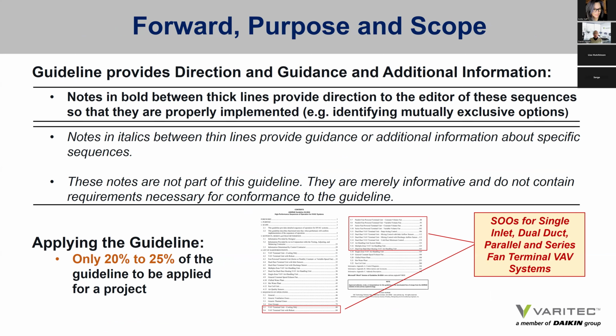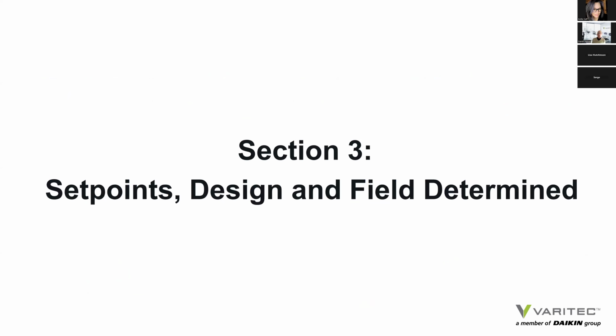The guideline provides direction and guidance and other additional information. The directions are in bold, black font, and the guidances are in italicized, non-bold, regular font. So consequently, when you look at the guideline and take into consideration the directions and the guidance clauses, as well as the varying types of VAV systems, chances are, if it's applied on a medium pressure VAV system, only 20 to 25% of the document will actually be used. So it can be a little daunting to look at over 300 pages of sequences, but once your system is defined, it really does narrow what it is that you'll be looking at.